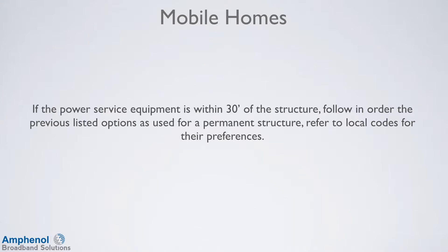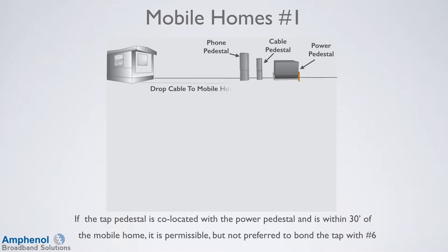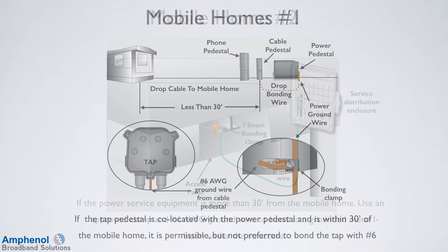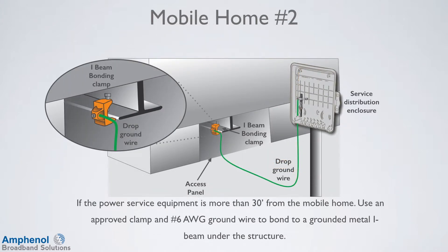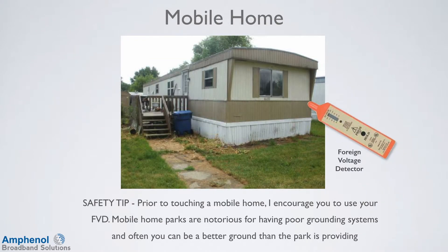With mobile homes, if the power service equipment is within 30 feet of the structure, follow the order of the previously listed options as used for a permanent structure. Refer to local codes for their preferences. If the tap pedestal is co-located with the power pedestal and within 30 feet of the mobile home, it is permissible but not preferred to bond to the tap. If the power service equipment is more than 30 feet from the mobile home, use an approved clamp and a number 6 gauge ground wire to bond to a grounded metal I-beam under the structure. Safety tip: prior to touching a mobile home, use your foreign voltage detector, as mobile home parks are notorious for poor grounding systems, and you can often be a better ground than the park is providing.